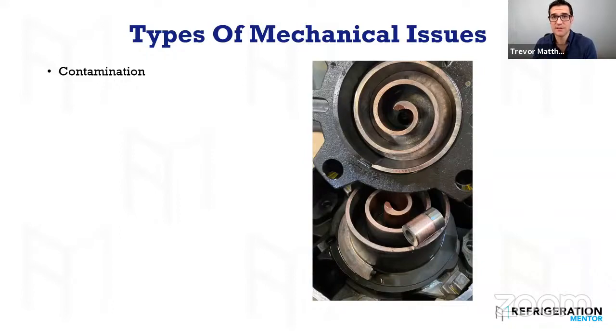But you need to do this, because if you don't, this is exactly what happens here. If you only pull it down to 2 bar, or if you don't pull it into a deep vac, you're going to get copper plating. It happens if you get moisture in the system. That's why you put sight glasses on the system, to see if you have moisture in the system. That's the whole point of a sight glass. A lot of people think it's to check your oil, your refrigerant level. Yes, it does that too, but it's really there to see if you have moisture in the system.